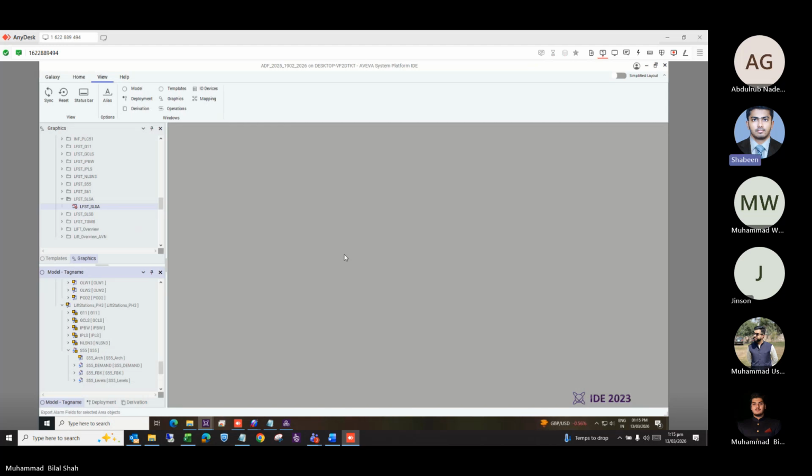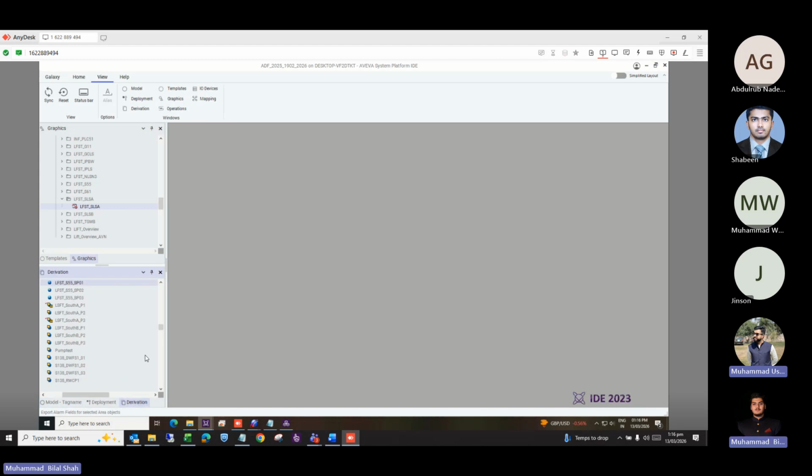And also once we do a change, how we save it, like it should reflect on the runtime. Yes. So changes are of two different types. One are graphical changes. If you want to make any graphical change, you can just open the graphic, do the changes, and save and close it. It will be saved in that graphic. But a very important point that you asked, these changes will not be reflected in the runtime. For runtime reflection, you need to redeploy your runtime application to that specific node. For example, Bilal, can you go down to the viewer application?